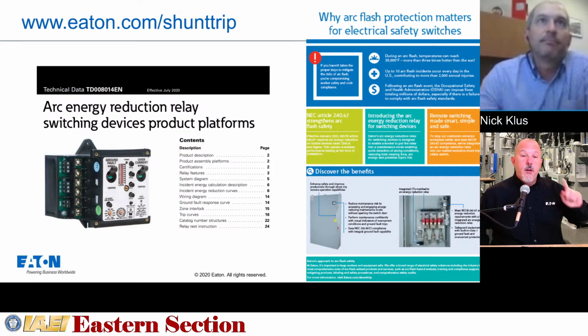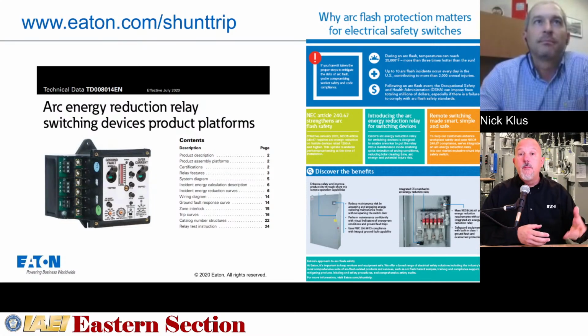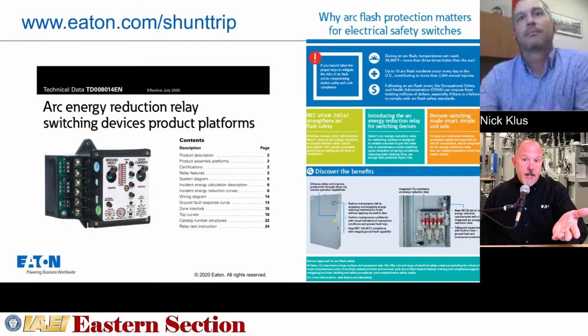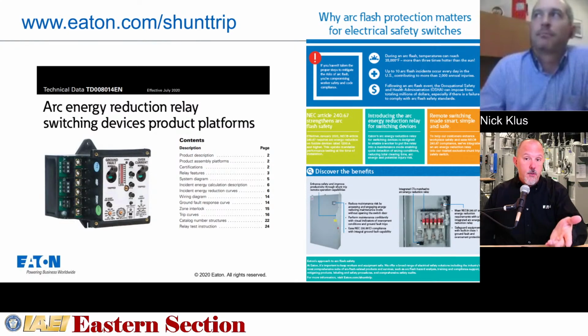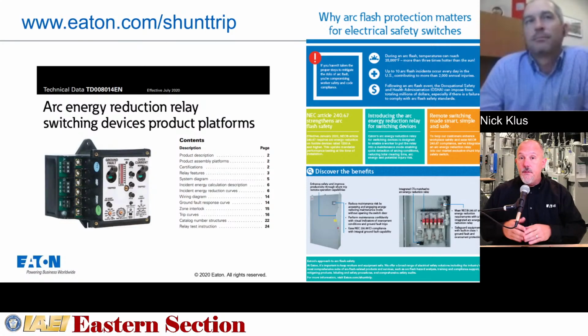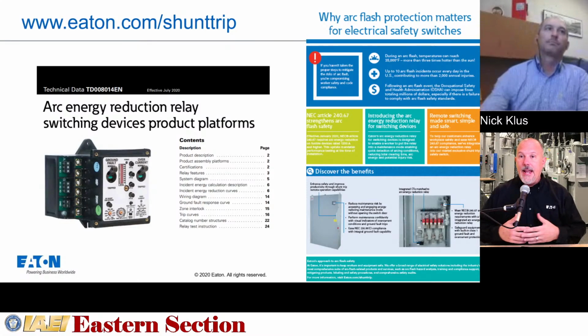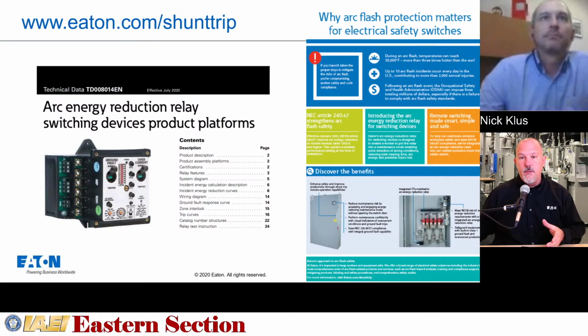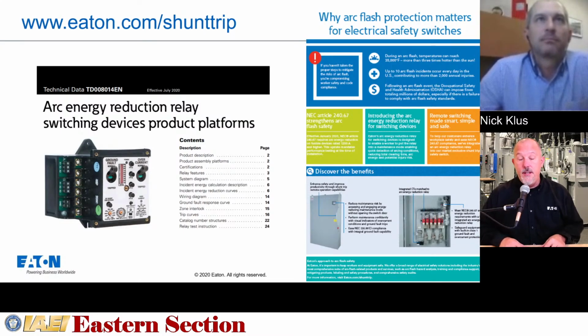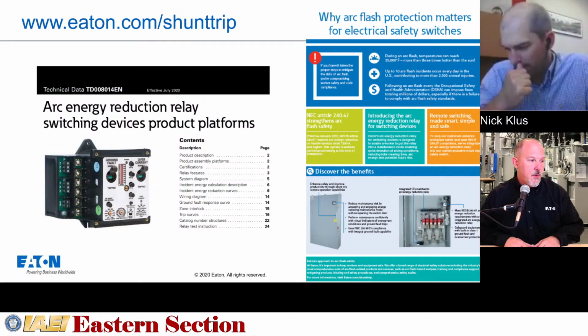Yeah, that's a good point, Nick. And also, we know that if you have available fault current, you can calculate a minimum arcing current. With these products, whether it be a breaker or a fusible switch that's using this relay, if your fault currents are above a certain value, you can estimate or calculate what the maximum calories would be to determine a PPE level. For anything downstream at that next level of equipment, as long as the fault current is above a certain number and you have the arm switch on, then you can dress a certain way. That's the creativity that engineers and others can employ.